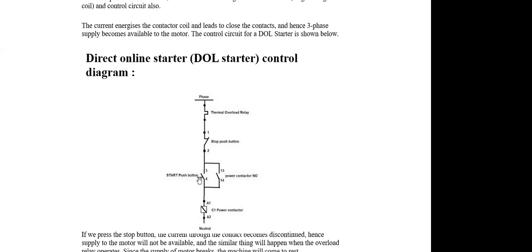I am pushing the start button here. It is making contact between 3 and 4. This contact is picked up and this auxiliary contact is held by this. So the motor is continuously running. And if I want to stop the motor, I put a stop button here. If I push the stop button, the current flow is disrupted. So the contactor is de-energized, the motor stops.